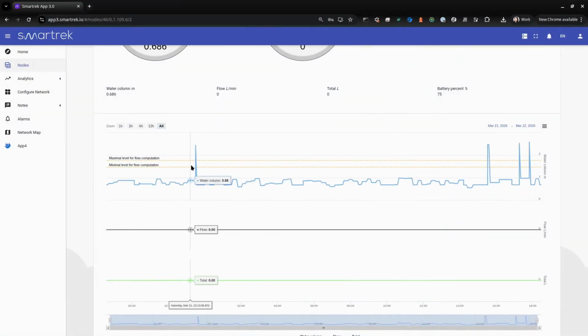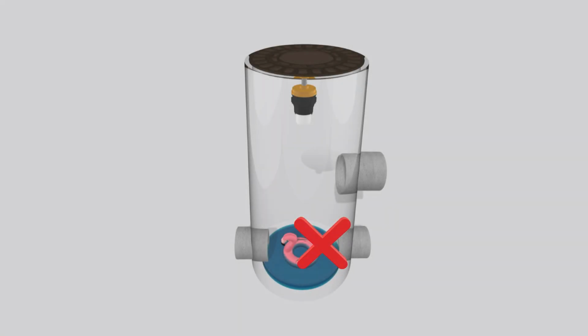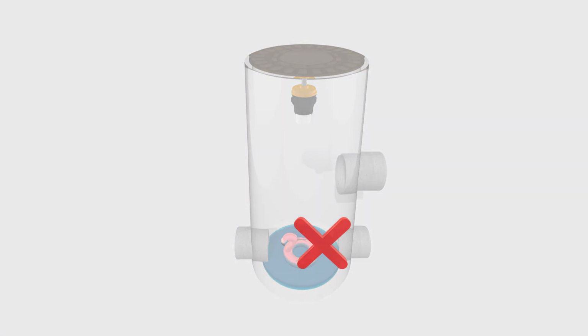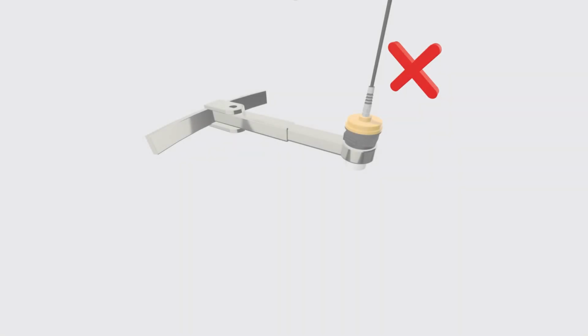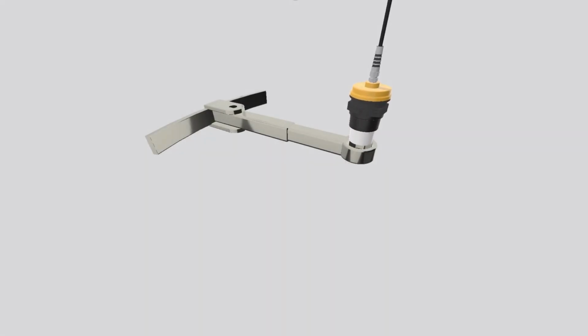If you observe sudden fluctuations in the water level readings, then verify your probe installation. Make sure there are no obstacles in the probe's path, that it is positioned away from the walls and the ladder, and that the probe is not screwed into the metal bracket.